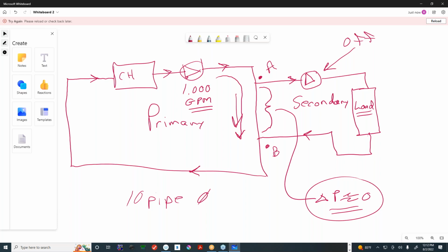So if we were running 1,000 gallons per minute, I have a little chart here that I'm going to look up in a second. So if I have 1,000 gallons per minute, I'm going to go back here, put in 1,000. And I'm running a pipe that's, let's say I had an 8-inch pipe. My velocity would be about 6.42 feet per second. And my pressure drop would be about 2.18 feet per 100 feet. So you can see that the pressure drop is about 2 feet, if this was 10 pipe diameters, and we just said this was 8-inch pipe, so that means it would be 80 inches.